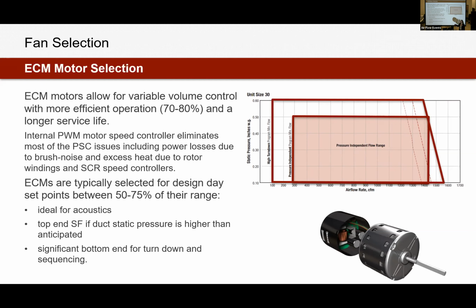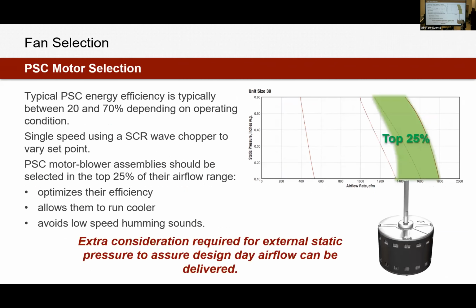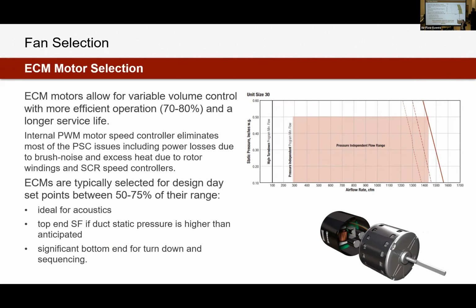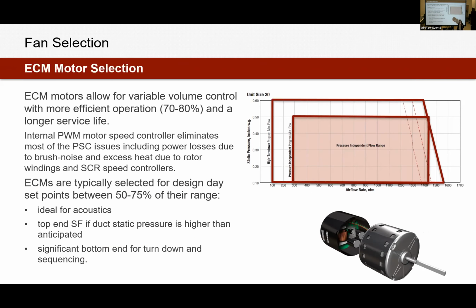The downside is that your fan airflow will track in that diagonal line. Less than the PSC, you can see it's not quite as tapered off as the PSC, but we do have some reduction. As that filter's loading, as our pressure's increasing, we will see a little bit of a reduction, which ultimately will change that top end possible airflow. Both programs have their places, both are really useful, but it is something that has to be determined before ordering the equipment.